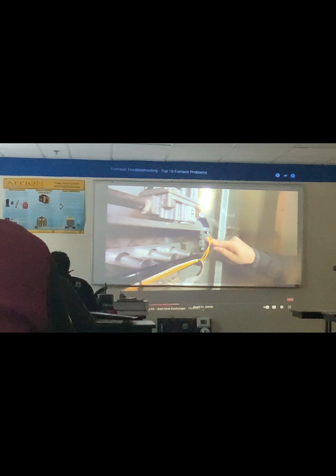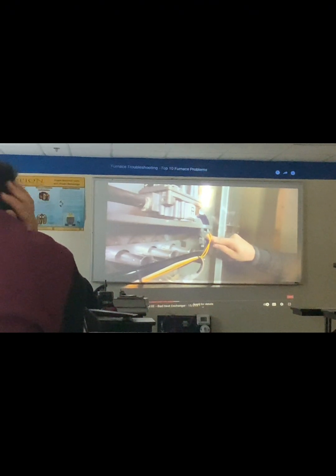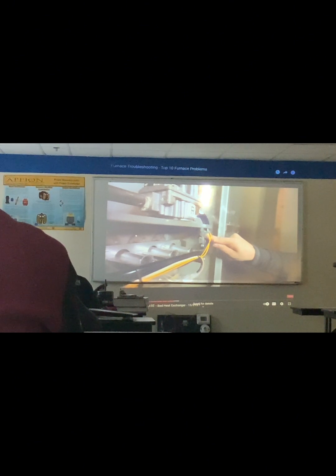And the reason you have to manually reset as a technician is because you see where they're placed outside the heat exchanger. This is a heat exchanger with a, what are these? Igniters. That ain't no igniter. What are these three things? We haven't covered that yet. Burners. And so this heat exchanger is behind this wall. And so these are rollout switches, meaning they're safety switches if flame rolls out of the internal furnace. I think we might have talked about it in the past. If the flame rolls out, don't put your face in the way, and these switches were open, it doesn't take much heat. And that's what I told you when my eyelashes got burned off, right? That flame rolled out of that furnace.